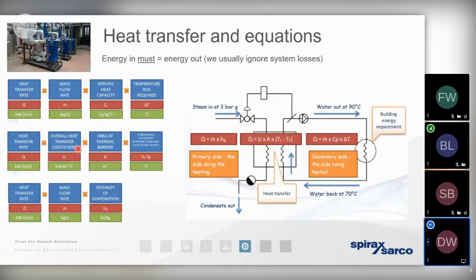Now, if we're looking at an existing heat exchanger, it's highly likely that that information will be badged on the unit already. If not, we can refer to the manufacturer's thermal energy data sheet. Or if we're sizing a totally new heat exchanger for a new application, we can go back to first principles and we can calculate it from the appropriate sizing charts. We want to then multiply that by the heat transfer surface area of the heat exchanger itself. We refer to that as the A value. Again, that can be badged on the unit itself, or we can take it from a manufacturer's thermal energy data sheet in the case of an existing heat exchanger.